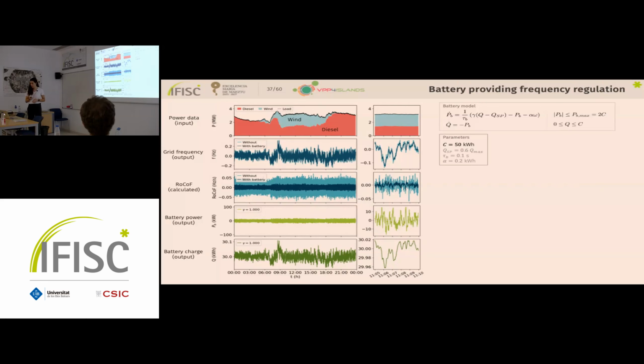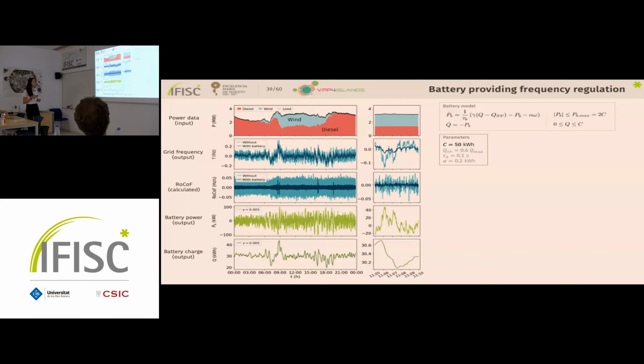When we decrease gamma, we are able to reduce the frequency fluctuations more, and also the ROCOF is more reduced. But the cost is now having larger deviations of both power and charge. If we reduce gamma even more, the fluctuations are much more reduced, but now the battery is even reaching its limits in some cases, and that is why we observe these peaks in the ROCOF.